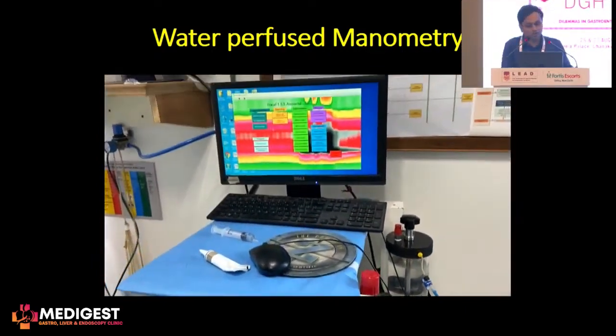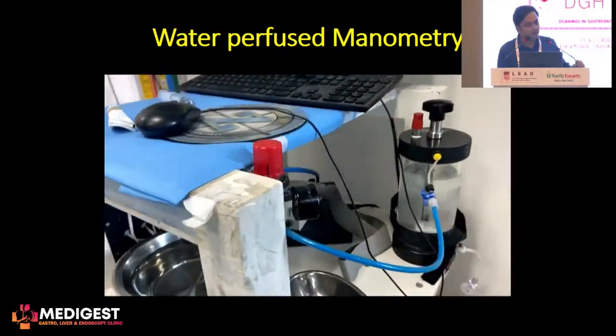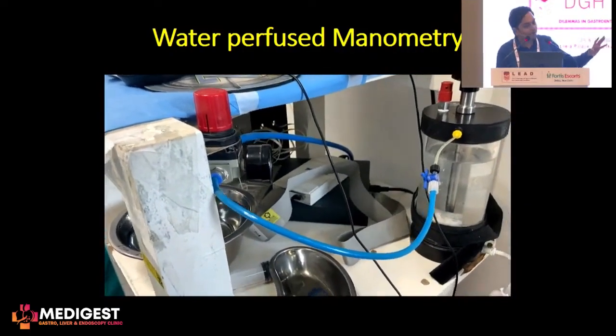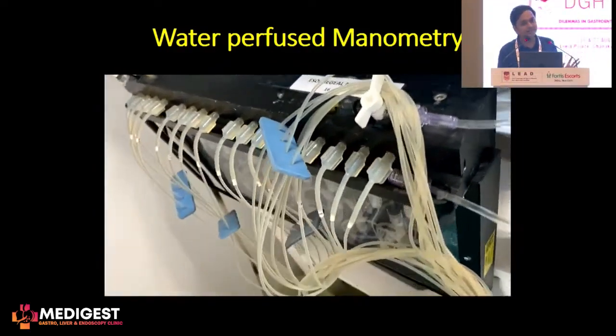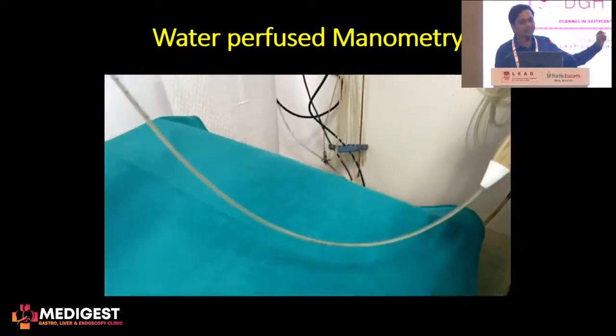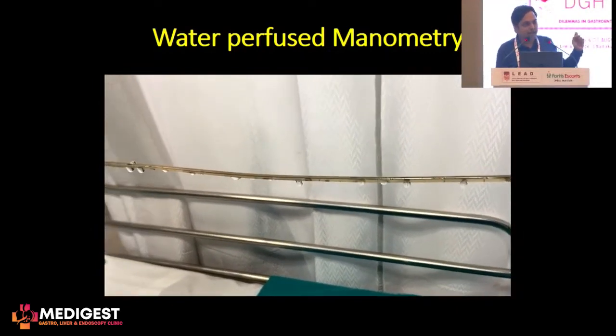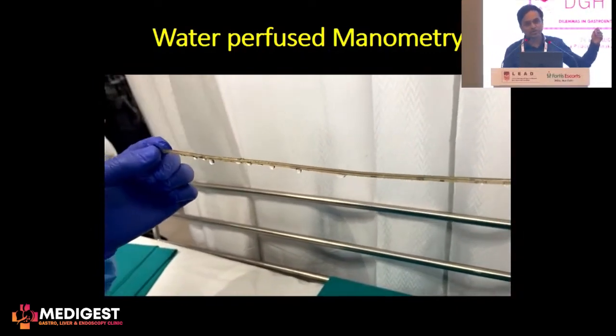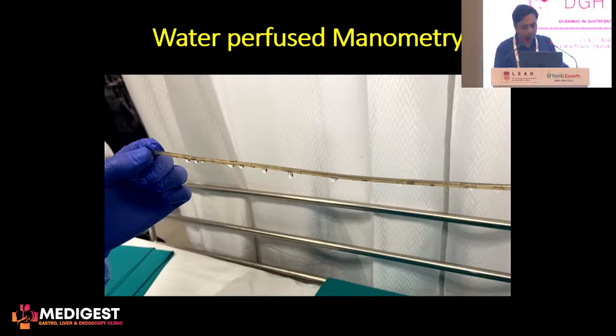In a water-perfused manometry system, every system has a chamber containing water which is propelled under approximately one atmosphere of pressure. This goes through an intricate set of capillaries, which are eventually connected to a single catheter through which water drips at a specific rate. Whatever pressure is offered to the flow of water in the area of interest is converted into colors, and those graphs are then evaluated in the manometry output.